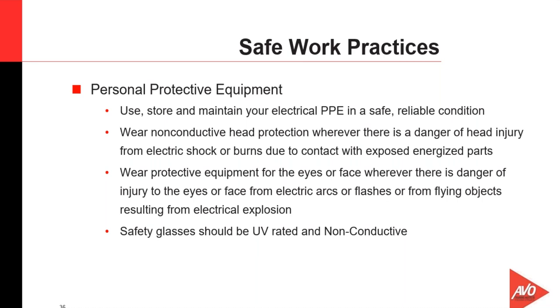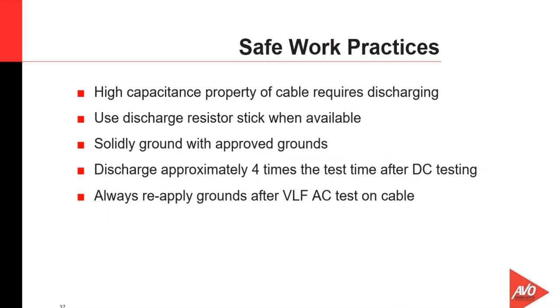More safe work practices for testing high capacity cables, where we have been testing power cables. They're fairly capacitive in nature. If these cables have been tested with high voltage, then probably they retain some of that charge, or can. So when discharging medium voltage and high voltage power cables after testing, we should use a discharge resistor stick to slowly bleed the charge off the cables themselves. Then we can solidly ground with approved ground devices.